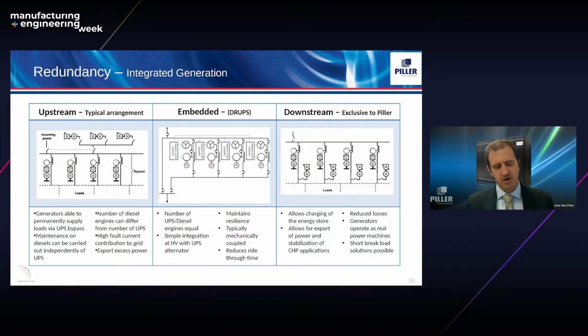But in a lot of sites, it can't always be avoided. Where you do integrate your diesel, you have some options, and that can influence how you operate your system. The conventional configuration sees diesel generators integrated upstream in a centralized generation plant. This allows easy export of power independently of the UPS plant. The direct connectivity isn't there, but it does mean you need some ride-through time to get between mains and generator, and for switching of the supply to connect through to your UPS.